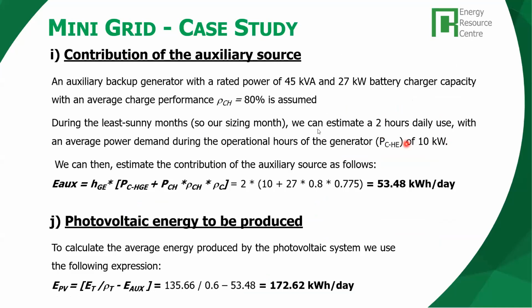So for the use of the diesel genset, with the diesel generator, we want to charge our batteries and also be able to supply a little bit of the demand when the PV system is not enough. I insist, December, January, and February. So for these 3 months, we will have an effective net energy demand that will need to be covered with the generator. That will be the addition of the power demand from the community and the battery charging demand, okay?